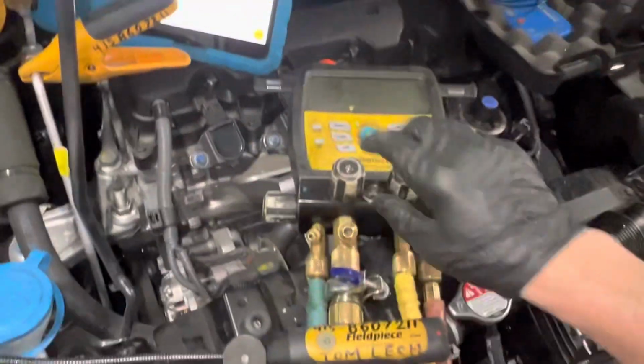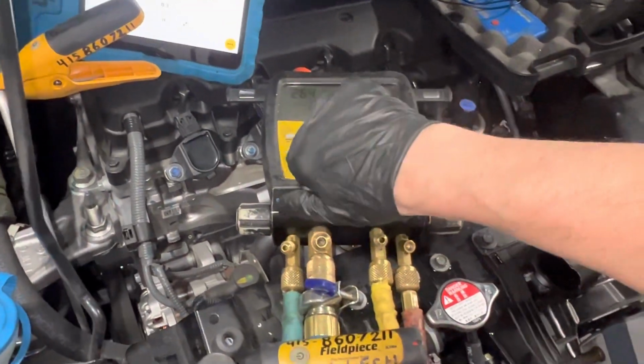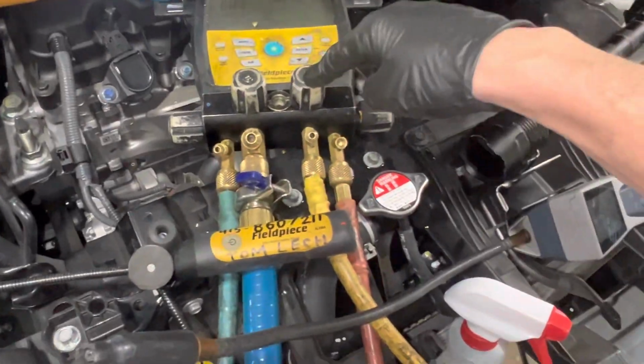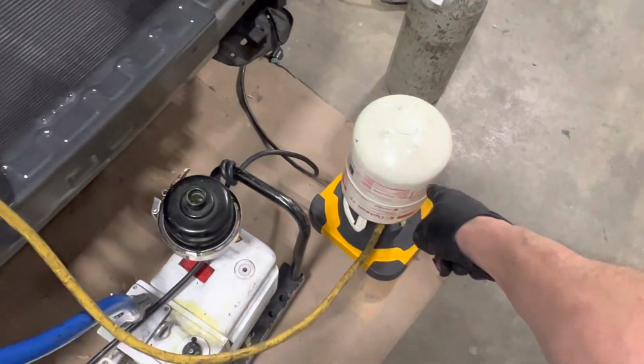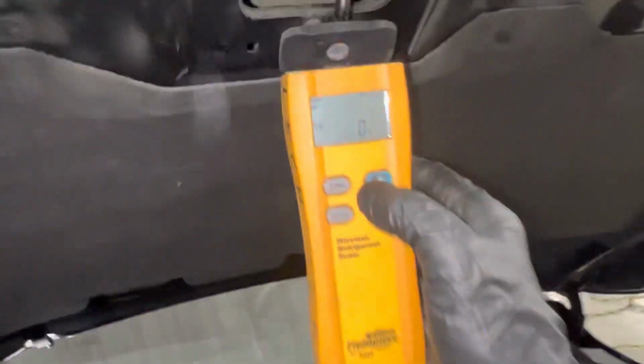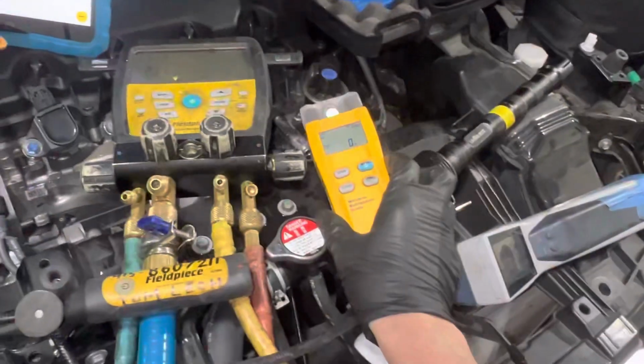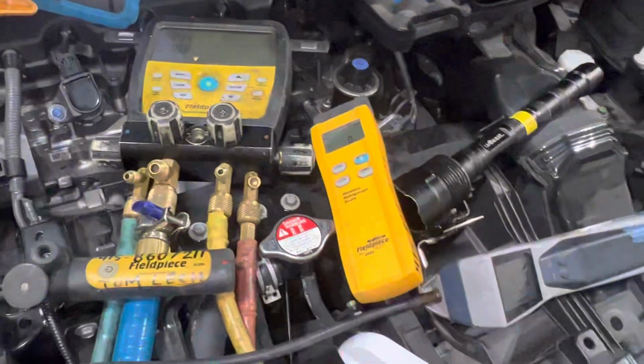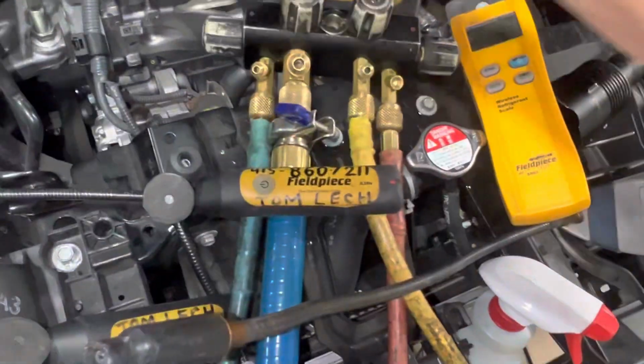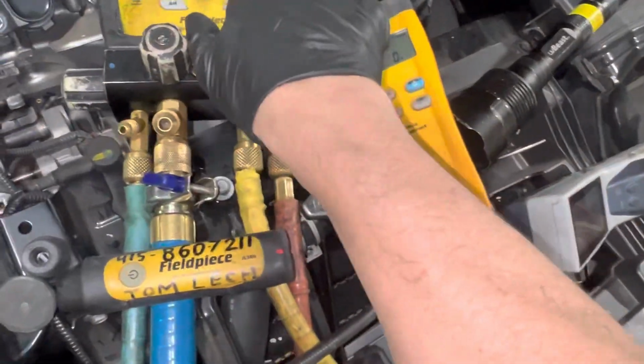So we have the low side off, and we're going to kill the vacuum here. Vacuum is off, and we already have the liquid on the scale, weighed and zeroed out. Let's put that right here so we can see both at the same time. We have the high side open. Remember, we need roughly 445 grams of YF refrigerant.